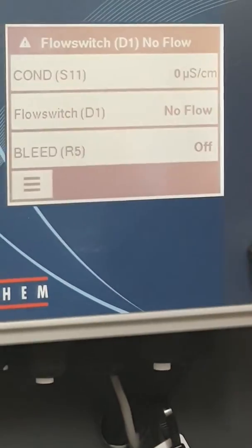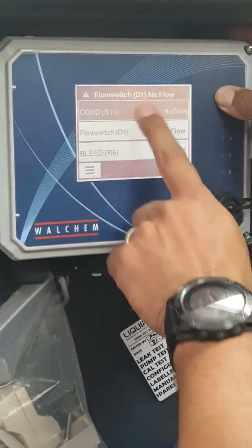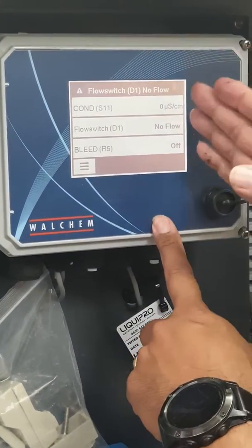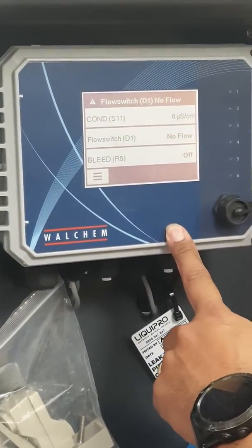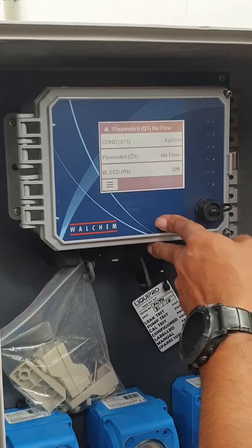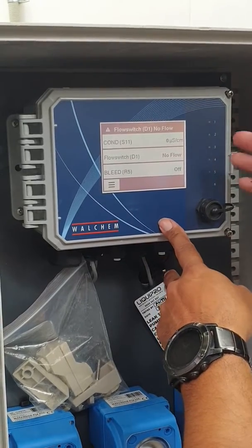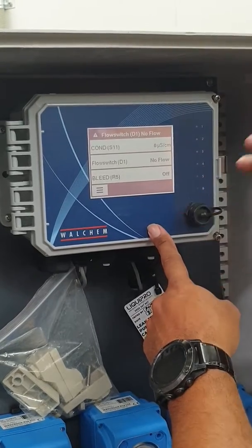This is just a quick overview of the controller — the WCT 600, or W600 Vision. What's really good about the W600 is it's a touchscreen, it has LED lights to show when a relay is activated, it has six relays, up to five digital inputs, and it can have up to four sensors depending on whether they are 4-20 milliamp sensors or standard Walchem sensors. If it's a standard Walchem sensor, you can only have two.